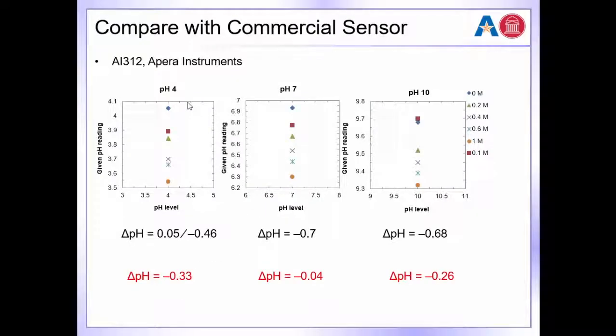But nonetheless, we took a commercial sensor and compared. We added different amounts of sodium to the commercial sensor, and we found that its pH also changed quite dramatically. For this one, pH is supposed to be equal to 7, and with different sodium it should still be pH equal to 7, but you can get pH equal to 6.3. So that obviously has error. But with this calibration, we can now bring that accuracy to a very confined area without being affected by the sodium. So even compared with the commercial sensor, our performance is still better.